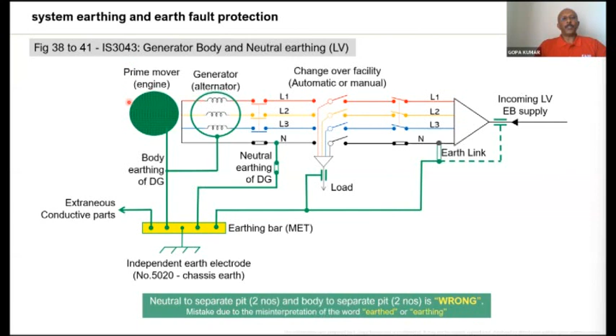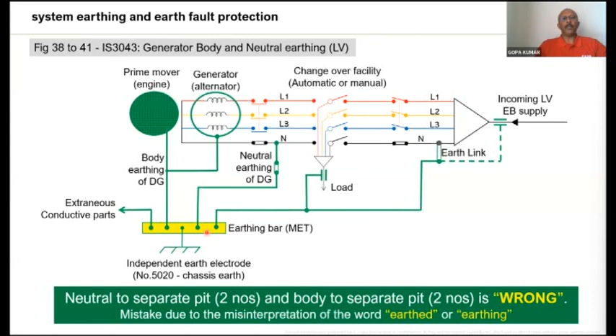Now, coming to IS 3043, which is the code of practice for earthing, figures 38 to 41 very clearly explain how to make earthing. You must interconnect every exposed and extraneous conductive part to an earth bus bar, not to the earth electrode. Similarly, another subject which needs a lot of attention is fault loop impedance. Fault loop impedance means the impedance of the circuit which decides the disconnection time of the protective device.